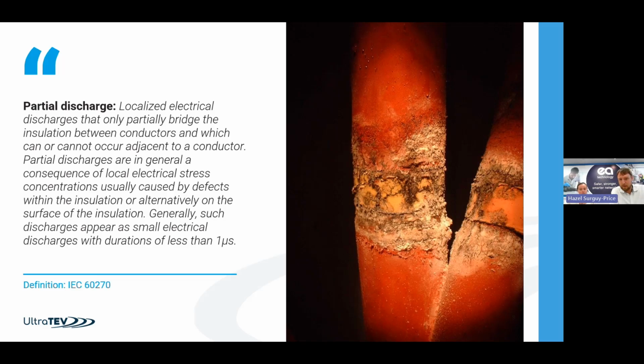It'll be a small spark, electrical stress around the area, and it'll slowly eat away at the insulation. Once it starts, it'll continue to deteriorate. It can happen anywhere in the insulation system - in cables, terminations, cable joints, or within the surface of the equipment, or even other fixed parts like bus bars. So anywhere in the HV insulation system where there's stress.